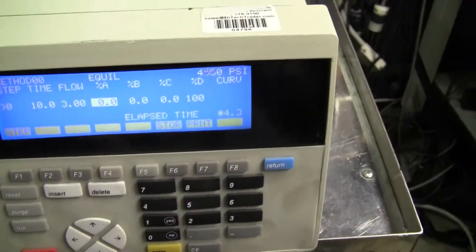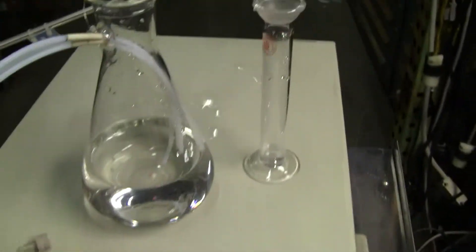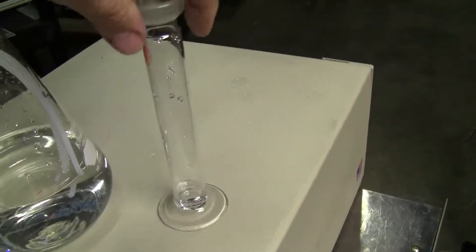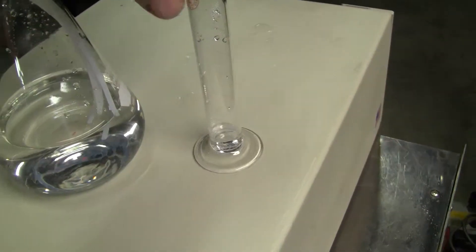You can hear the clicking of the valves. We've tested that out. We've also done a pressure test — it's holding quite nicely. We've done a volumetric flow test, and we've achieved our desired results of 3 mLs per minute.